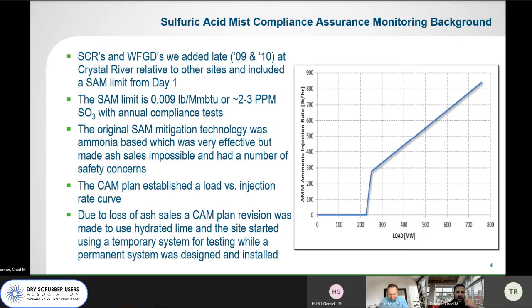The original sulfuric acid mist mitigation technology that was installed was an ammonia-based system, which was very effective, but essentially made ash sales impossible. On top of that, there were safety concerns associated with an ammonia-based system, through dewatering systems and ash handling, all of which have ammonia present, and through excursions could have high levels of ammonia off-gassing.